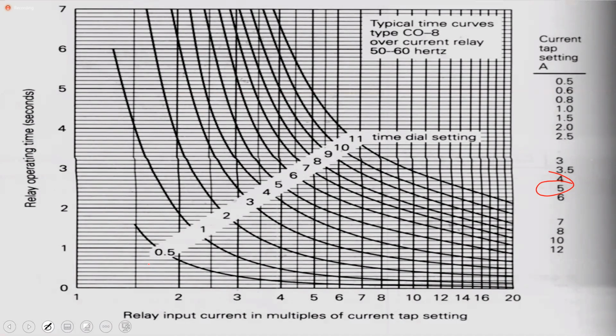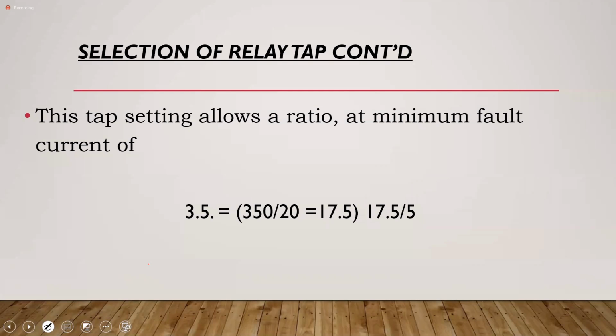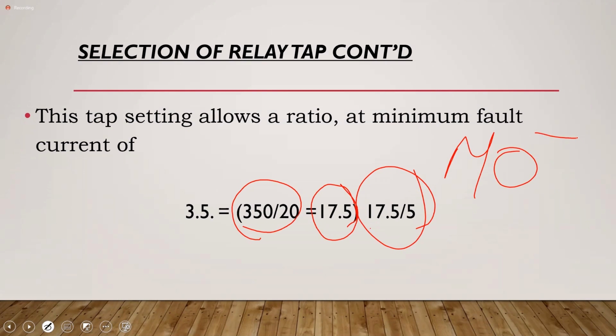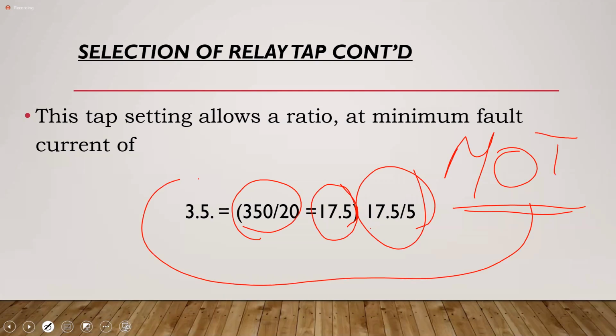So I'm going to now look at the minimum fault. The minimum fault was 350 amperes, yes? So for the minimum fault, with 350 amperes on the system, the current from the CT would be 350 over 20, which is 17.5. Everybody agree? But the 17.5, which is now the output of the CT, when I divide it by the tap, I get multiples of tap. And that multiples of tap is 3.5.